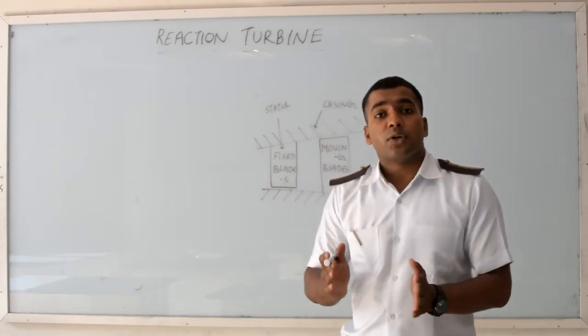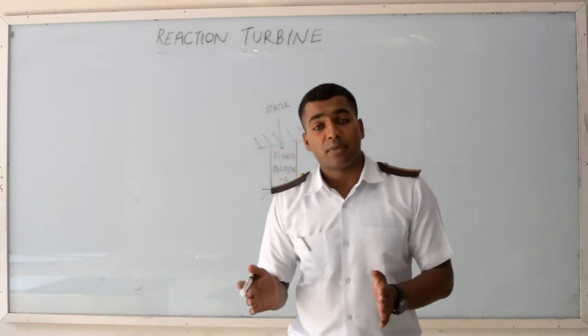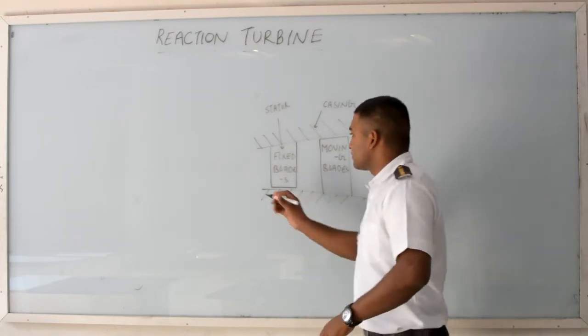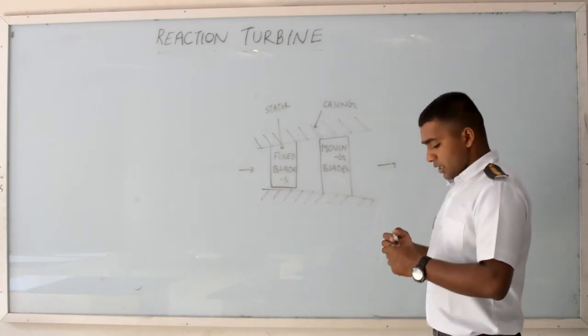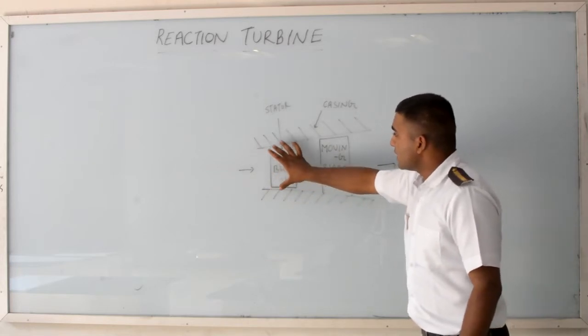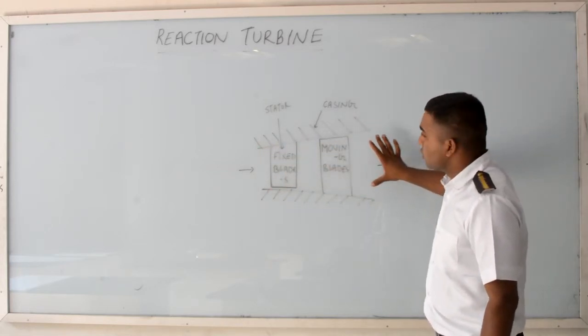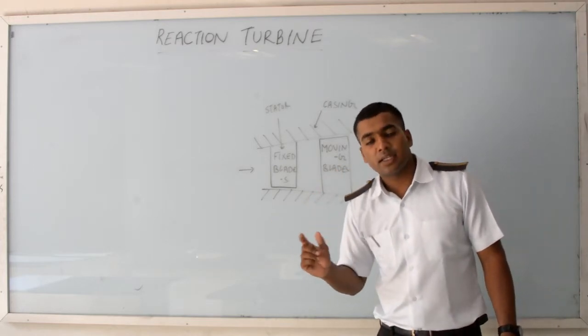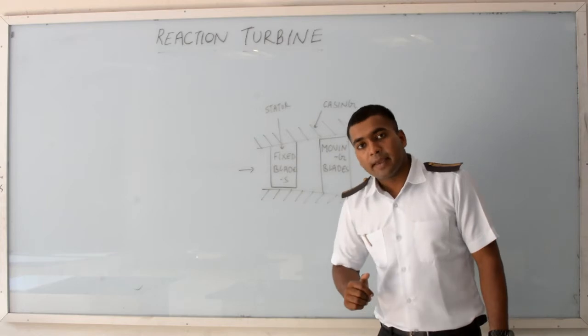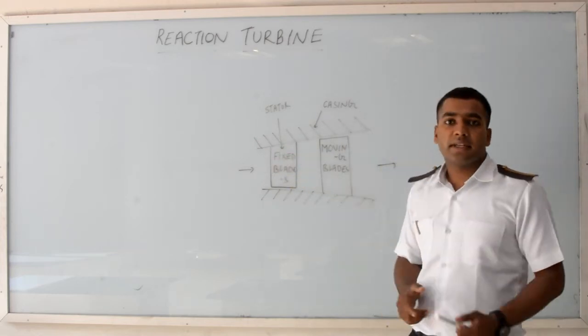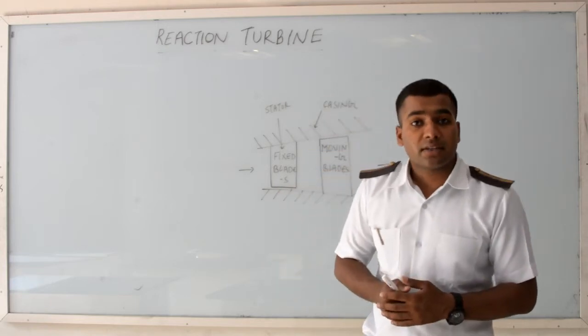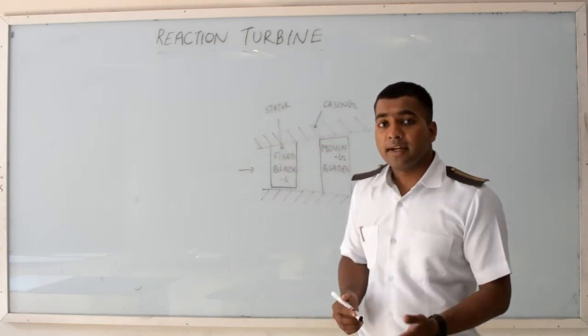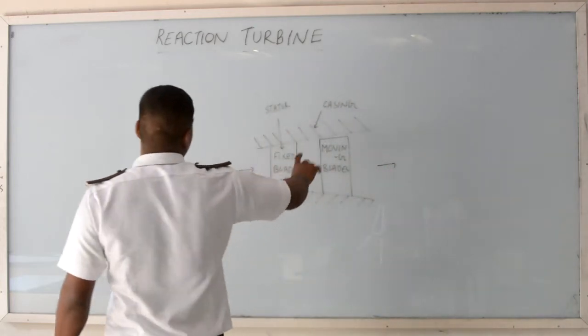In the Reaction Turbine, the area between two consecutive blades does not remain the same — it is of converging type. As you can see from the diagram, this is the inlet and this is the outlet, and the area is of converging type, changing from inlet to outlet. Since pressure is inversely proportional to area, the changing area means the pressure will change everywhere. That is why in a Reaction Turbine, the pressure changes in both the stationary blade and the moving blade.